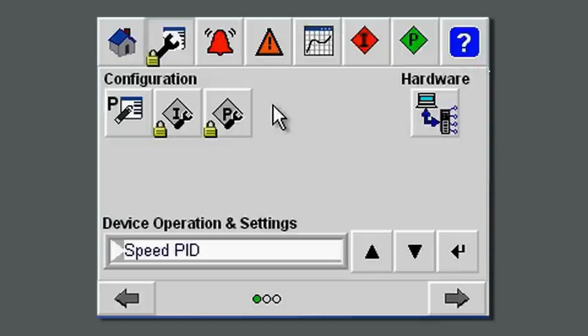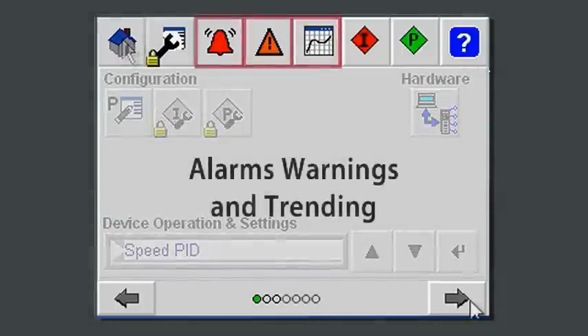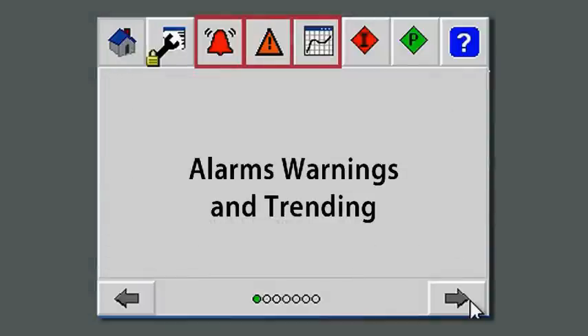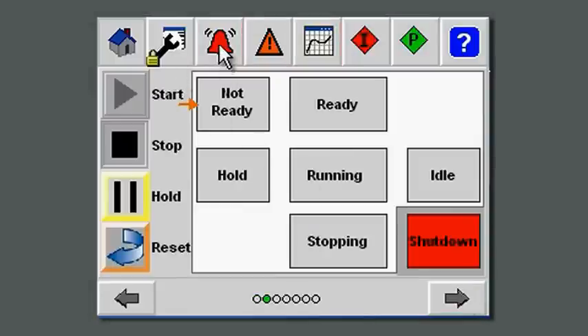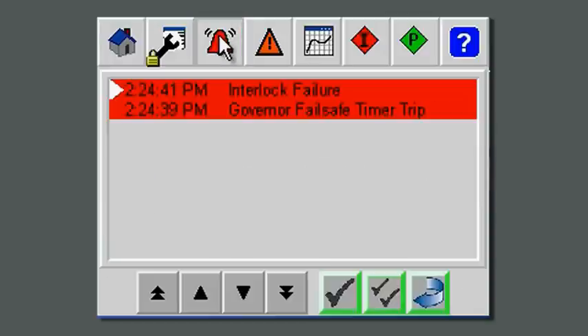When you're in running, this is the alarm page. As you look at the alarms, you'll see the 128 most recent alarms that have occurred. They're kept in a circular queue within the governor, so you can go back in time. Each alarm has the time of the event recorded along with it.